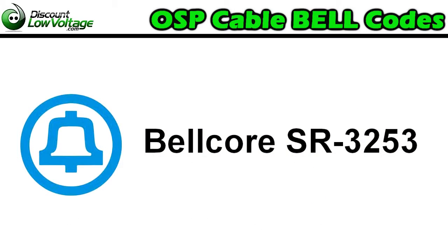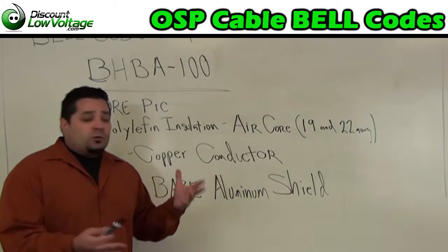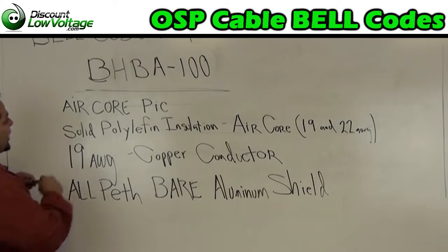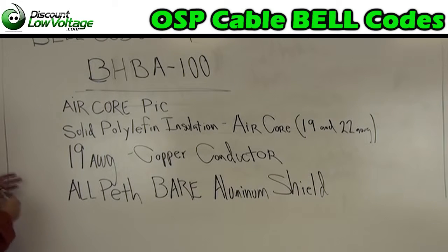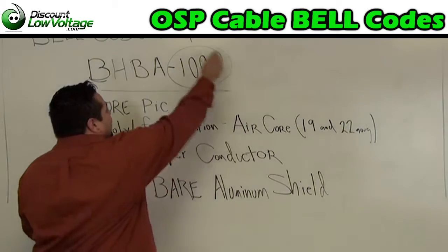All the codes we just went through are based on ICEA Publication P-61-694 and Bellcore SR-3253 Issue 1. According to our code BHBA-100, we have an air core PIC with solid poly insulation air core for 19 and 22 gauge cable. We do have a 19 gauge copper conductor, an ALPETH bare aluminum shield, and a 100 pair cable.